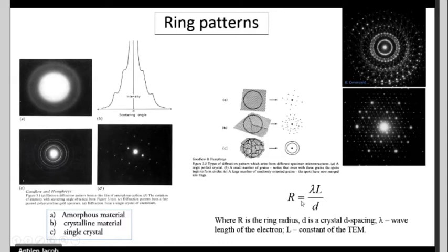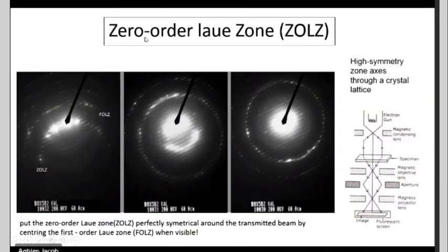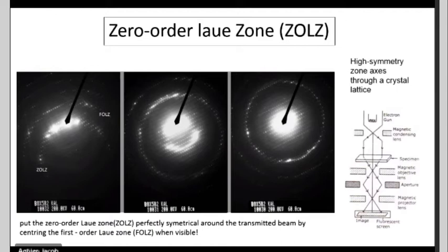The ring radius formula is: ring radius = lambda × L / d, where L is the camera length and d is the d-spacing of the crystal. One important concept to know is the zero-order Laue zone (ZOLZ). This is the highly symmetrical arrangement we can achieve by tilting the sample using the alpha angle, bringing the crystal to a perfect symmetrical orientation.